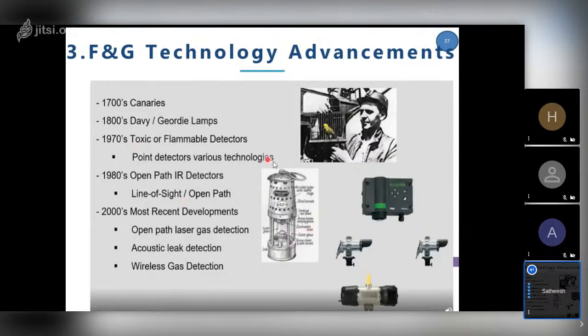Then in the 70s, we have the gas detector technologies we discussed so far, that is point gas detectors, toxic and flammable gas working. And in the 80s, we got the line of sight open path, which we also touched a little bit. And in the 2000s, the last 10 years, which is my area, we have open path laser. This is open path infrared. Now the laser came, and we even use it for H2S or toxic gas detection. We have open path gas detectors for toxic also, whereas here it's only for hydrocarbon.